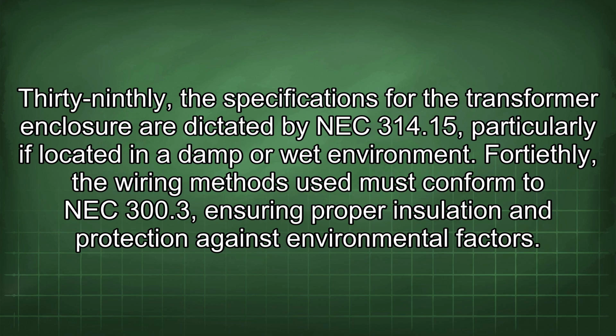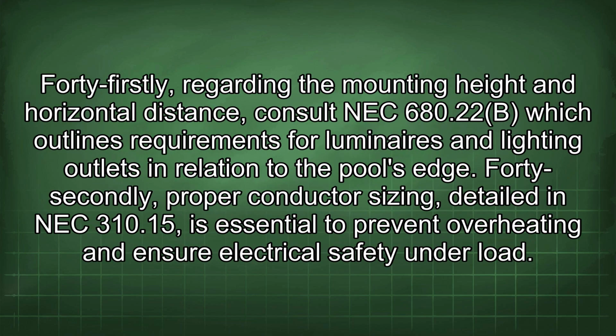40thly, the wiring methods used must conform to NEC 300.3, ensuring proper insulation and protection against environmental factors. 41stly, regarding the mounting height and horizontal distance, consult NEC 680.22(B), which outlines requirements for luminaires and lighting outlets in relation to the pool's edge. 42ndly, proper conductor sizing, detailed in NEC 310.15, is essential to prevent overheating and ensure electrical safety under load.